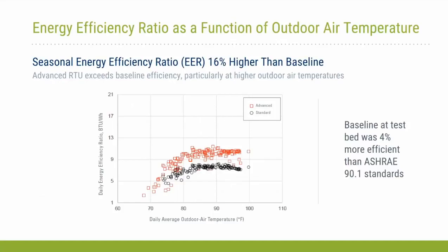So we did this, as I said, over a 10-month period. The graph that you see here is essentially daily energy efficiency ratio as a function of outdoor temperature. So the daily energy efficiency ratio is basically a ratio of total cooling provided by the unit over the course of a day to the total energy consumed by the unit, in kilowatt hours, over the course of the day. So on average, the high performance unit was about 16% more efficient than the standard unit, at least in this comparison. Next slide, please.